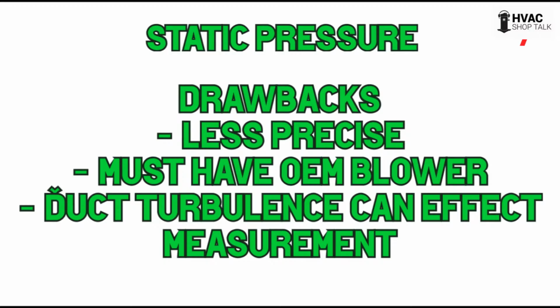If you have the TrueFlow grid on your machine, it doesn't matter what blower tap you've chosen. You don't have to put any static pressure probes in, you just have to measure. There are some pressure measurements, but with that device, you get a really accurate look at the amount of air going into the return side of your system. Static pressure is probably the best way to start measuring airflow because it's really attainable to everyday people.